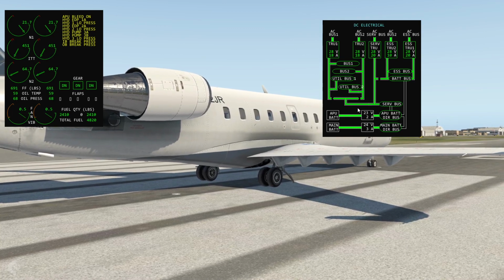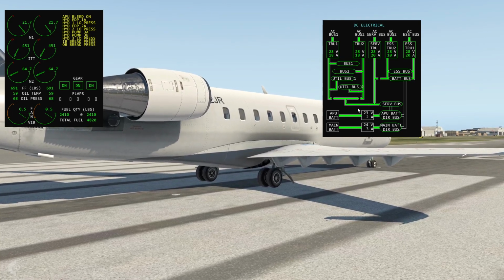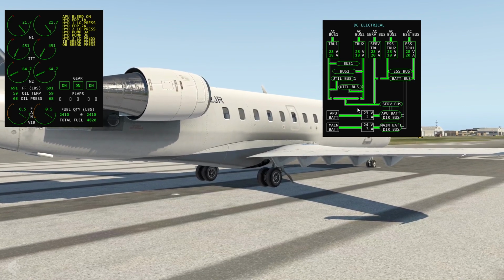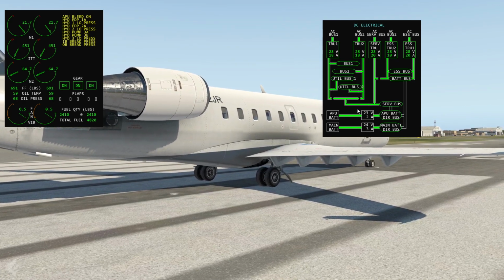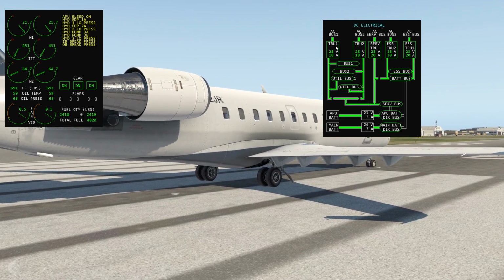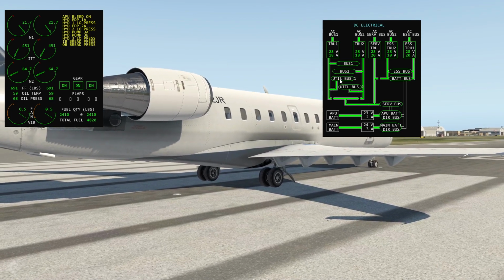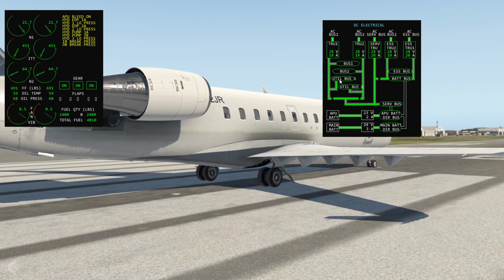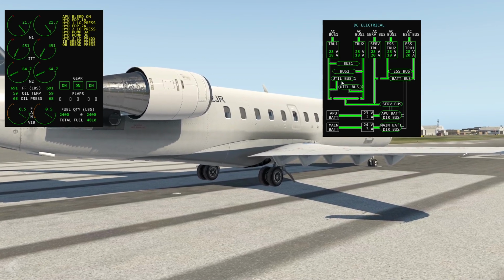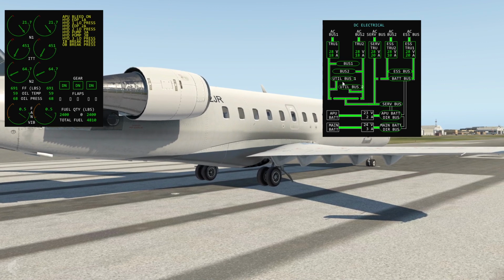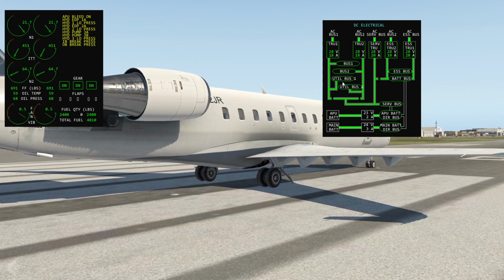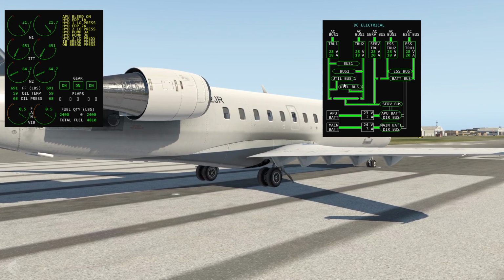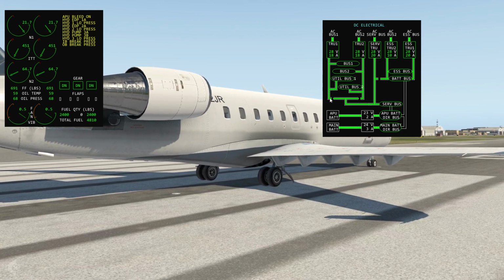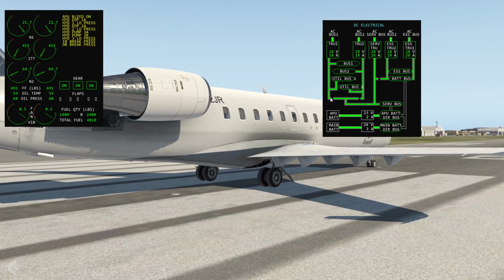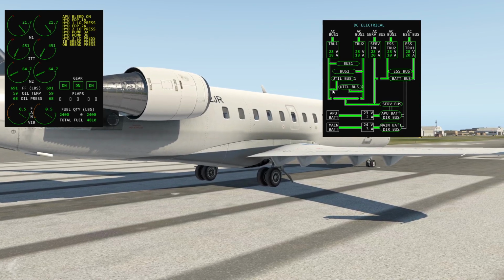So when the TRU that is associated with the DC utility bus fails, let's say this one failed, and that's associated with DC utility bus 1, the DC utility bus will be load shed to reduce DC electrical loading. And the DC tie contactors accomplish the load shedding. These right here. So you will connect this portion right here and we'll disconnect this portion.